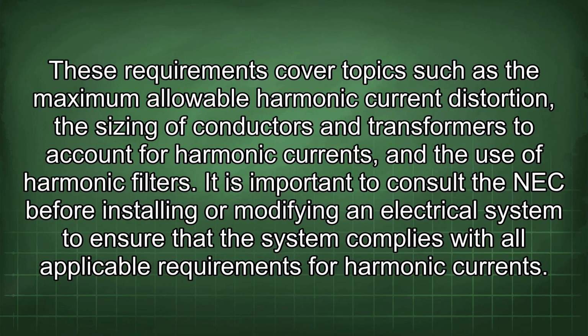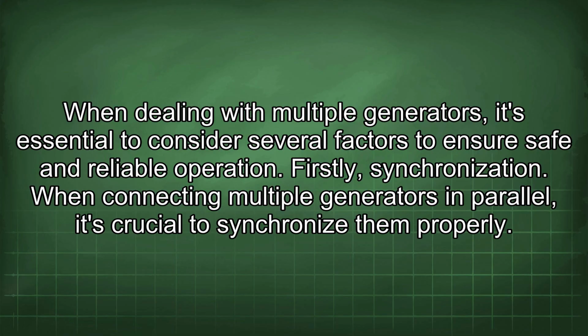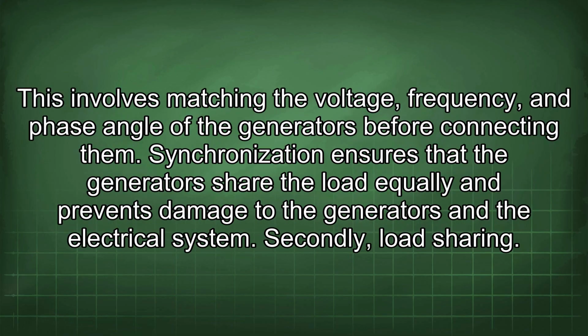It is important to consult the NEC before installing or modifying an electrical system to ensure that the system complies with all applicable requirements for harmonic currents. When dealing with multiple generators, it's essential to consider several factors to ensure safe and reliable operation. Firstly, synchronization. When connecting multiple generators in parallel, it's crucial to synchronize them properly. This involves matching the voltage, frequency, and phase angle of the generators before connecting them. Synchronization ensures that the generators share the load equally and prevents damage to the generators and the electrical system.